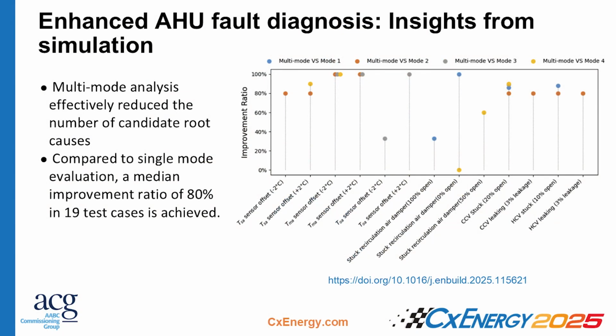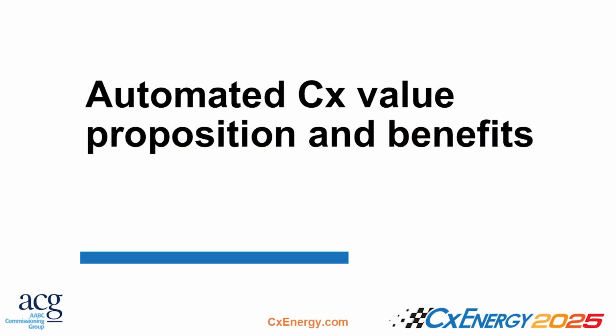So this is an example. This was a simulation-based validation of what we're talking about here, where we saw, out of the 19 test cases that we tested in terms of underlying faults that we impose on the system, on average, about an 80% improvement over just doing one mode and detecting the fault. Doing the multi-mode analysis improved our diagnosis success rate by 80%. So there's a DOI there. I think these slides are shared, but if you want to read that paper, please be my guest.